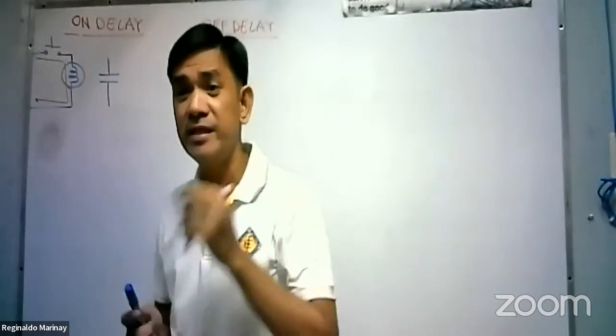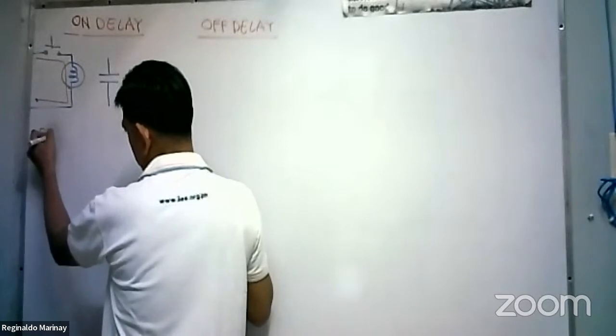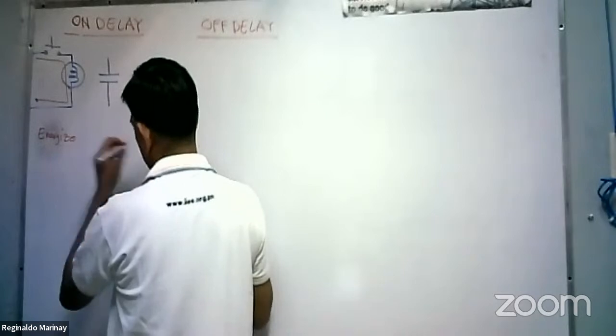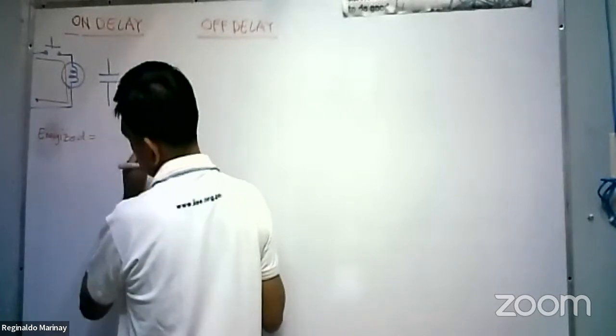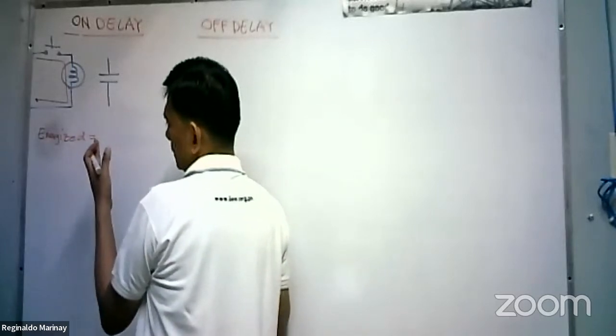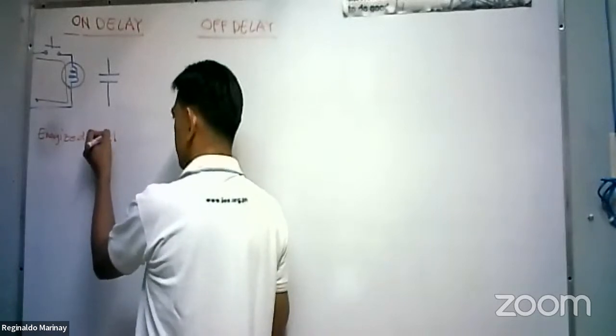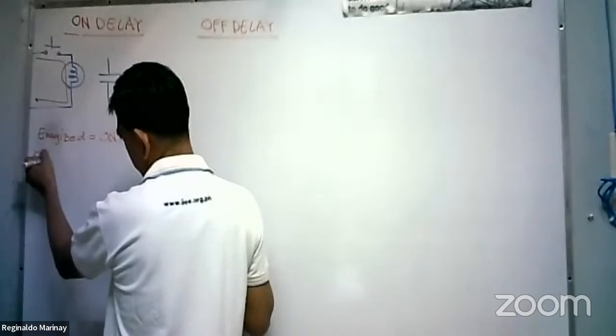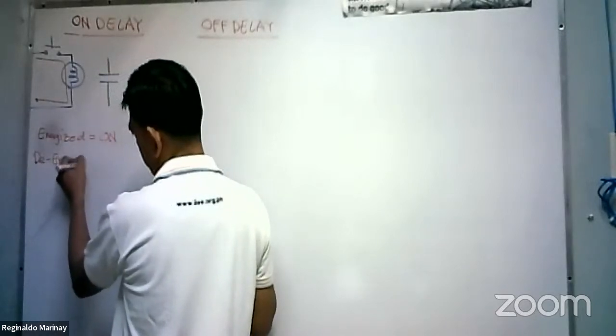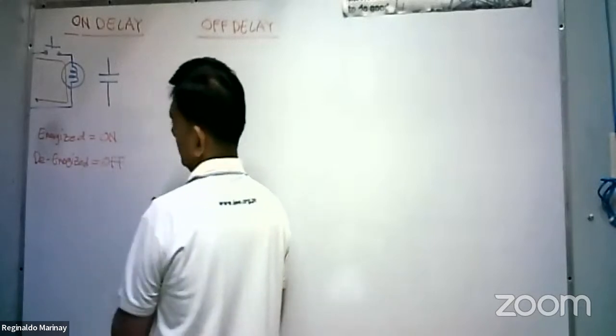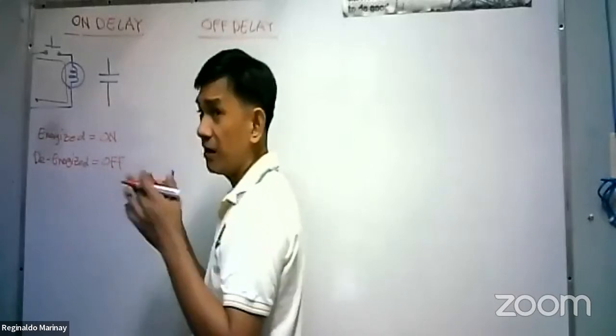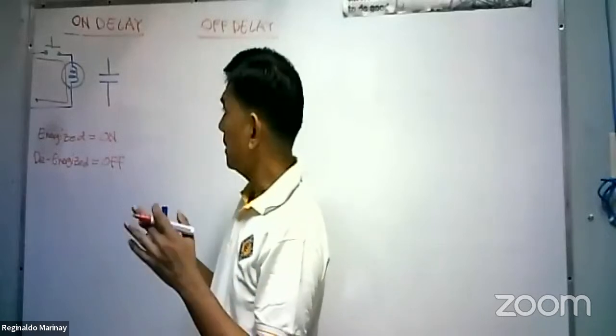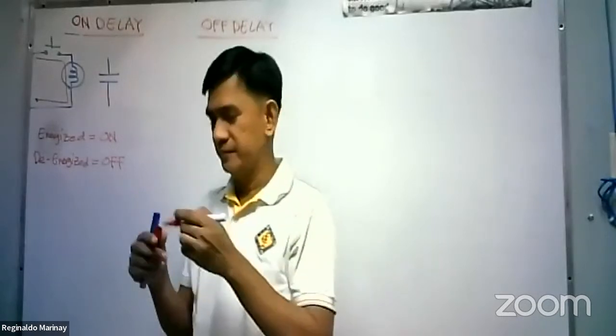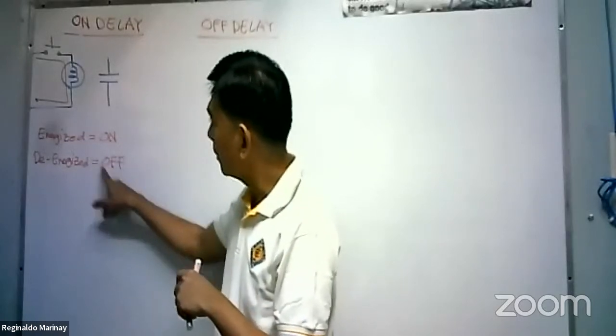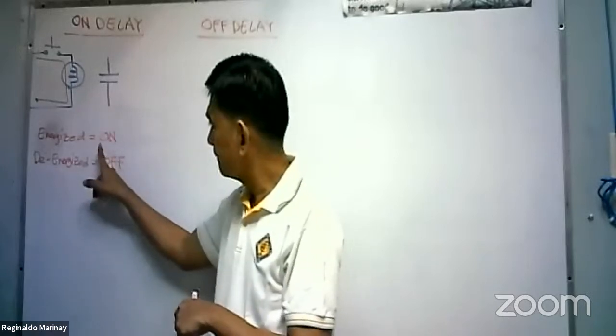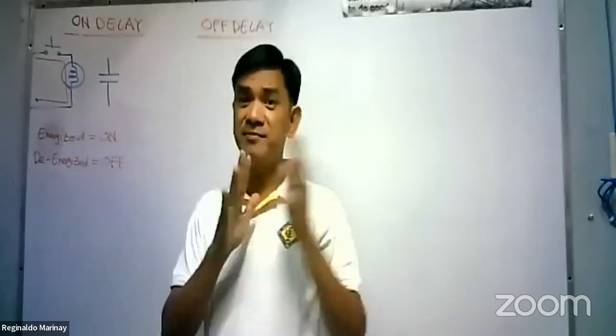From time to time, we'll be using the words energized and de-energized. Simply, if we mean energized, there is a current flowing. So let's say the switch is on, the circuit is on. If we mean de-energized, it simply means the circuit is off. Or let's say the timing relay is off, meaning there is no current flowing in the holding coil. If we mean energized, there is a current flowing to the holding coil. That's the difference between the two.